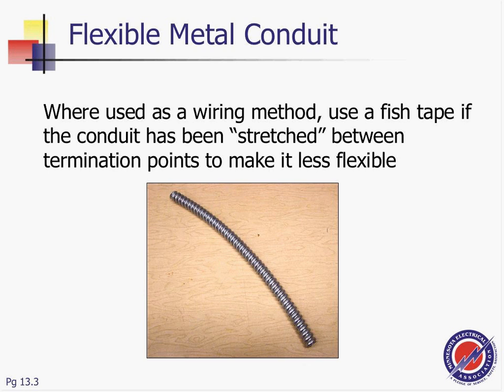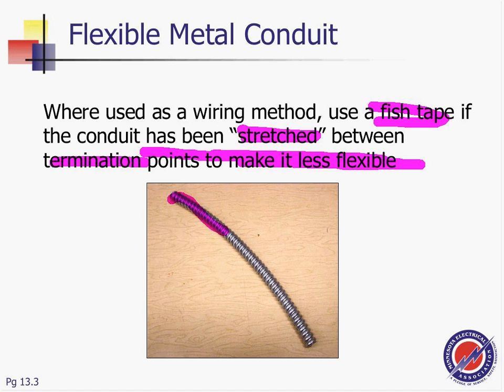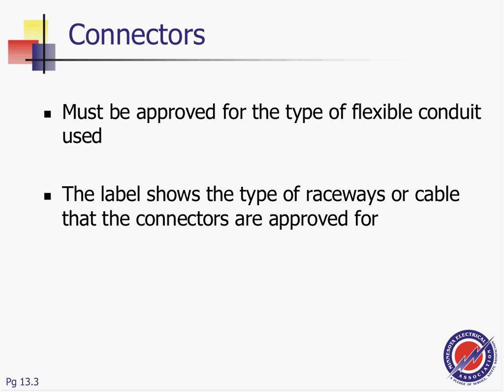It's really hard to pull these conductors if you're using them as branch circuits or otherwise. A couple of things about flex, guys, when used as a wiring method: use fish tape. Obviously, we said the conduit has to be stretched. Make sure it's stretched between the termination points to make it less flexible. That's the key point, guys. With the flex, the key is pulling conductors through it. If you're using it as an equipment wiring method, like they used in the 70s with Greenfield, it's really tough to pull conductors through it. So the key point: make it as straight as you can, if you can.